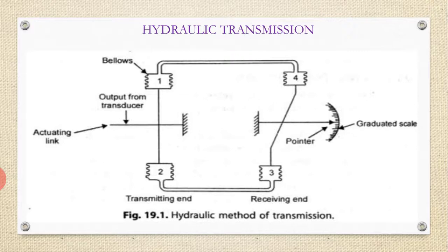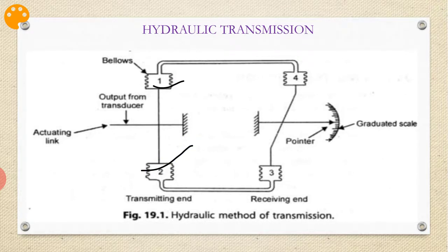The next one is hydraulic transmission. The figure shows the hydraulic method of transmission which is commonly used. Here, four bellows are employed — two are at the transmitting end and two are at the receiving end. The four bellows are connected by an impulse pipeline, and the whole system is filled with liquid.